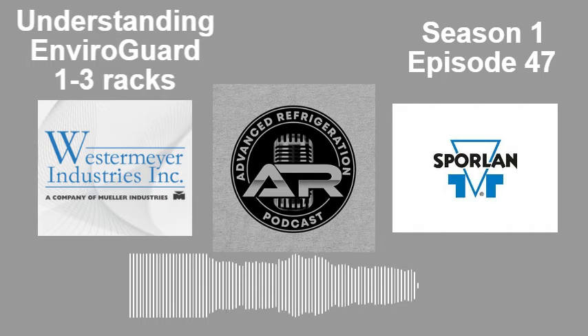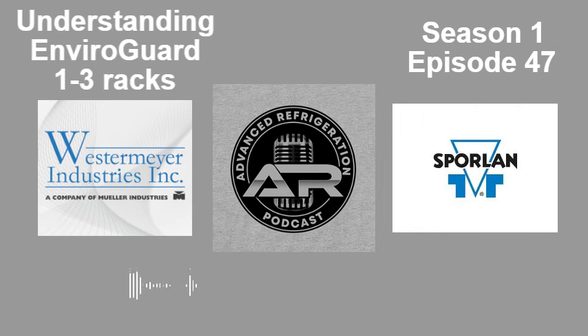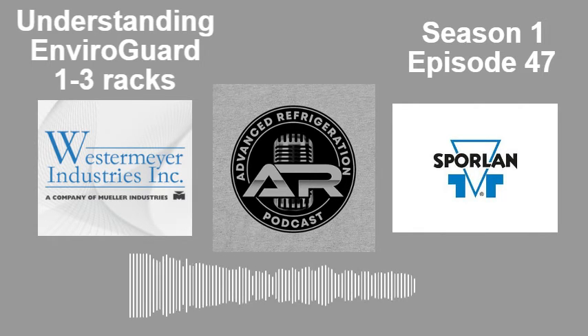I don't think I've ever had anyone overcharge. Oh, it happens at least once or twice a year up here. Especially with the apprentices, they see the receiver level and they freak out and think they're low on gas. If you're not above 70 degrees, you really shouldn't have much of a receiver level. But above 70, you should have 20% in there.